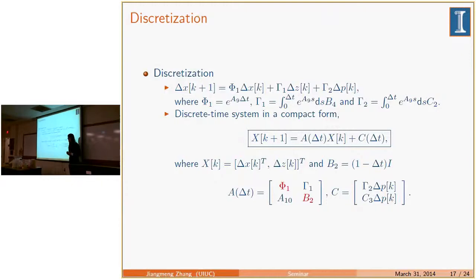It's very interesting that the phi 1 here is the system matrix for the original power system without AGC, and B2 here is equal to 1 minus delta T. This means that although the original system is stable without AGC, if our time interval is too large, this system matrix may become unstable, meaning the largest eigenvalue will be larger than 1.